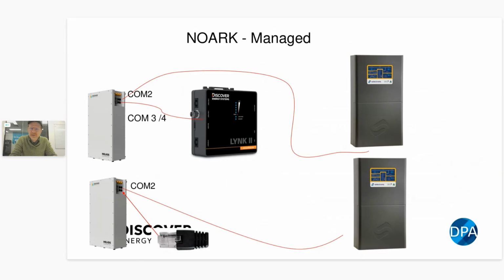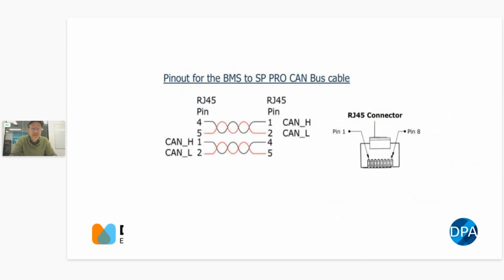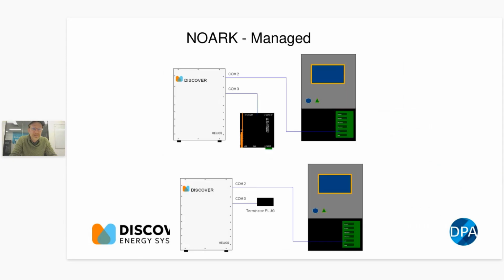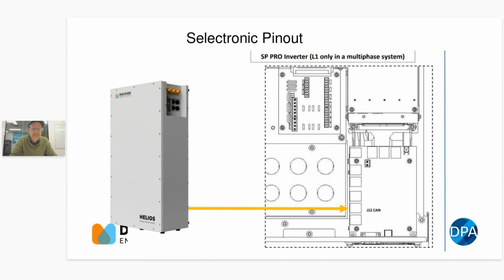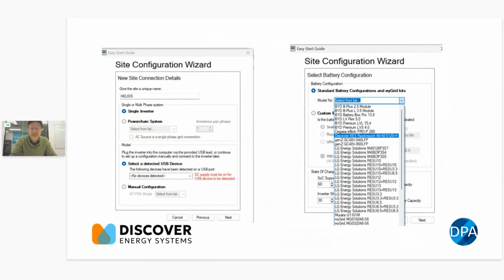Selectronic is the same thing. The Selectronic comes with that crossover cable, and that's just going into pins 1 and 2 on the Selectronic. And I think it's the second one from the bottom that you plug it into there. There we are. And as a quick way of setting it up for Helios until we've got the next wizard, you can just use the rack mount settings with a few adjustments. I'm going to be putting those up on our website the next couple of days. You're just throttling back the current basically, because there's a lot of DC ripple in a Selectronic, so you've got to make sure that the current is a little bit lower, because they use a magnetic breaker instead of a thermal breaker, and magnetic breakers are quite sensitive to the DC ripple.